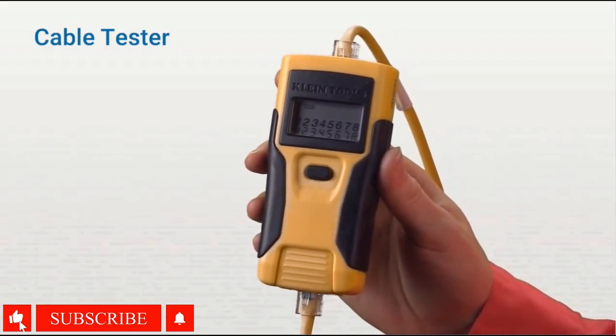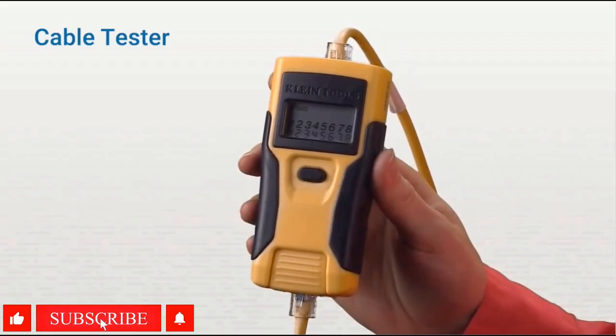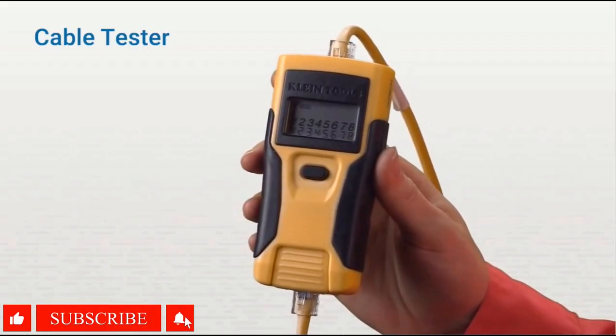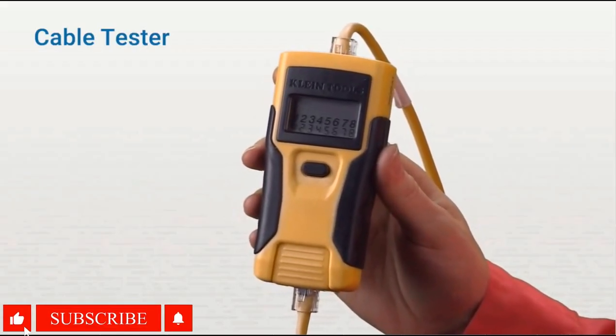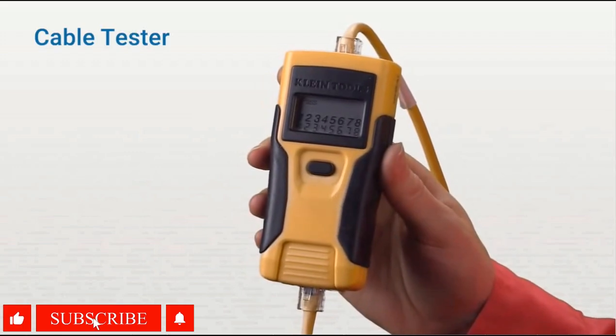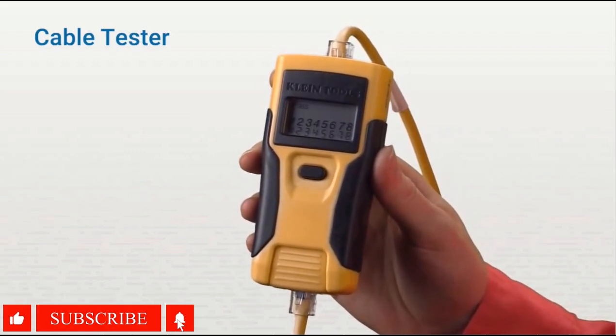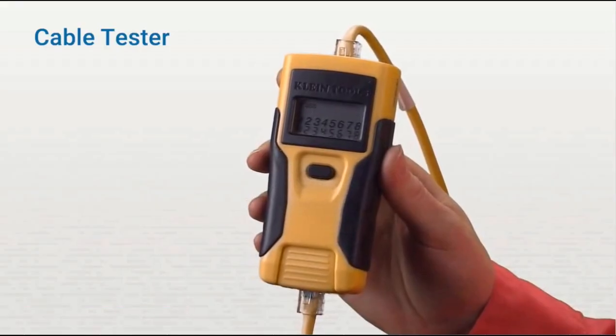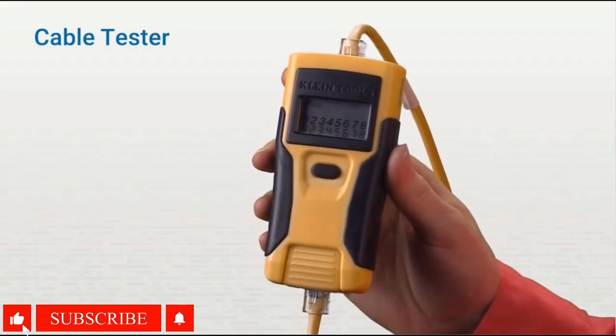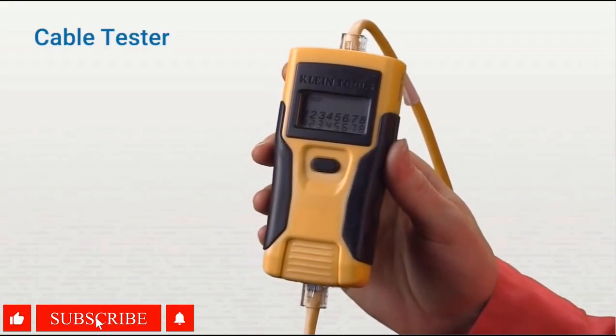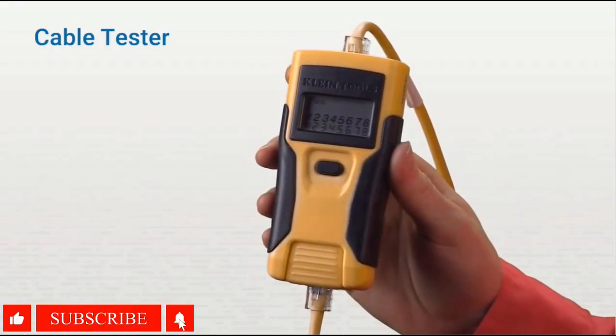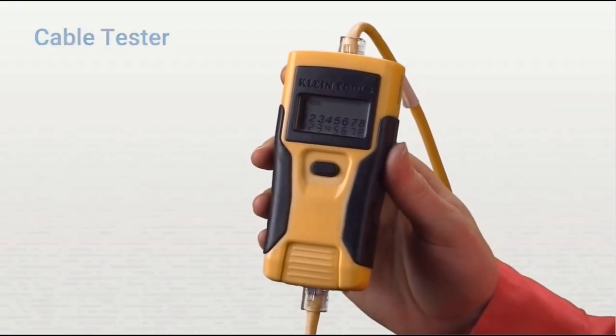TDR is an electronic instrument that uses time domain reflectometry to characterize and locate faults in metallic cables like twisted pair wire or coaxial cable. It can also be used to locate discontinuities in a connector, printed circuit board, or any other electrical path. If you're working with optical fiber, use an optical time domain reflectometer or OTDR.